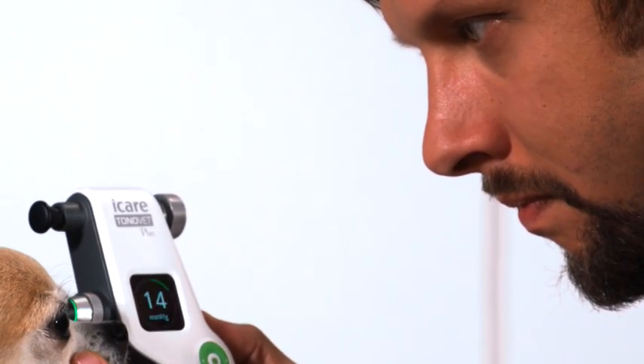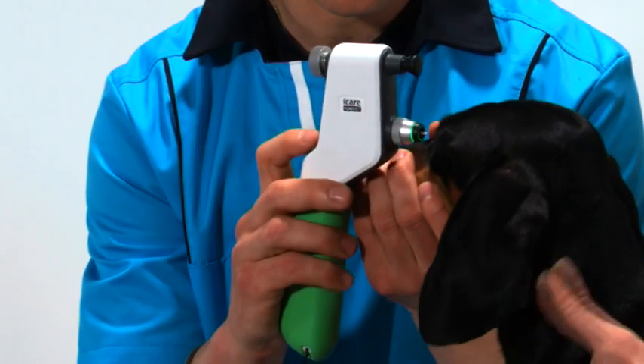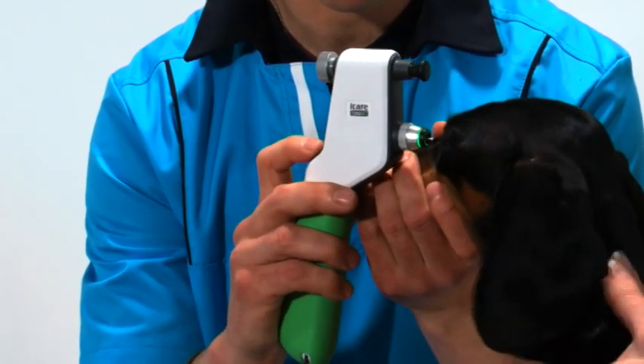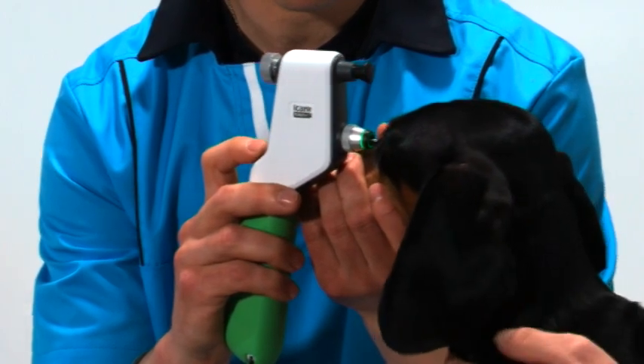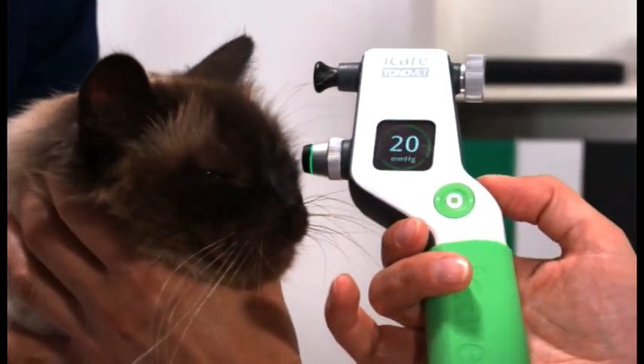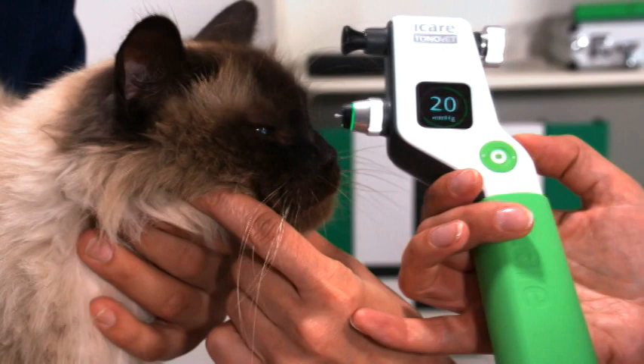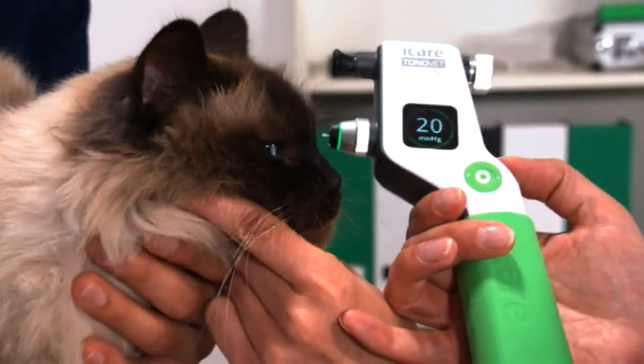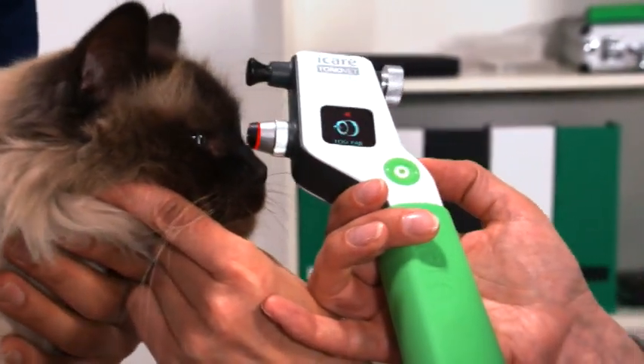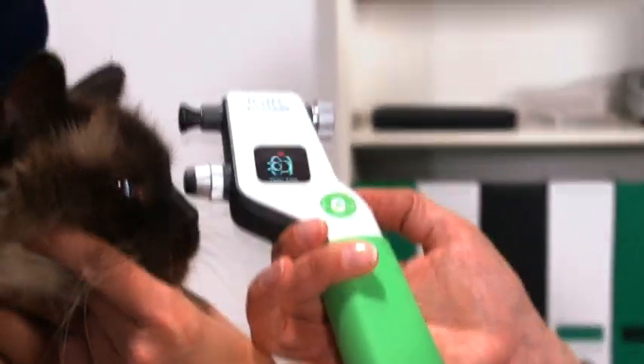The new TonoVet Plus offers many new features. The user-friendly display is more informative and easier to navigate. Indicator lights will actually guide your measurement without having to worry about the angle. A green light indicates that you are good to measure. A red light, on the other hand, indicates that you need to stop and reposition the device correctly at a 90-degree angle to the eye and parallel to the floor.